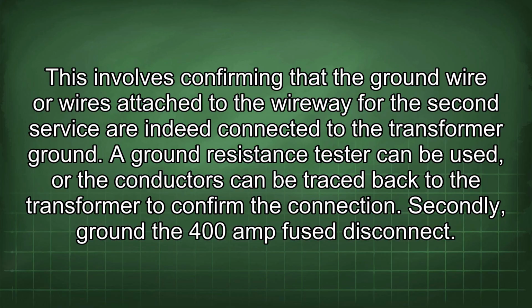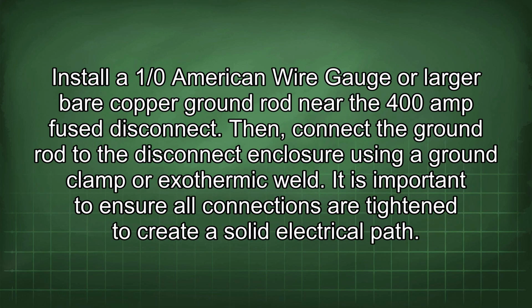Secondly, ground the 400 amp fuse disconnect. Install a 1/0 American wire gauge or larger bare copper ground rod near the 400 amp fuse disconnect. Then connect the ground rod to the disconnect enclosure using a ground clamp or exothermic weld. It is important to ensure all connections are tightened to create a solid electrical path.